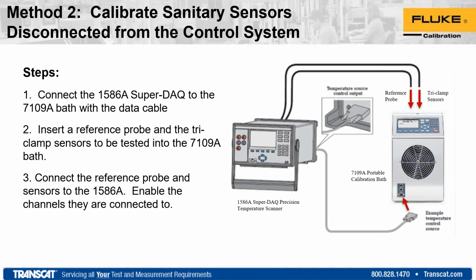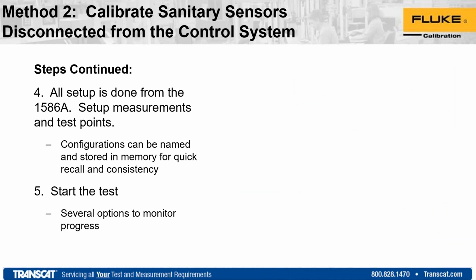So again, in this example, we've pulled the sensor completely out. We've now hooked in a reference probe as well as the device under test. We've pulled in a third piece of equipment, which we're going to use, our 1586A. And then we've also connected that to the 7109 or 6109 bath, whatever one you would be doing. In this particular example, all the setup is mostly done from the 1586A point of view. While the 6109 and 7109 baths have the capability to have their own internal programming and menus, we're using the 1586 now as the driver.